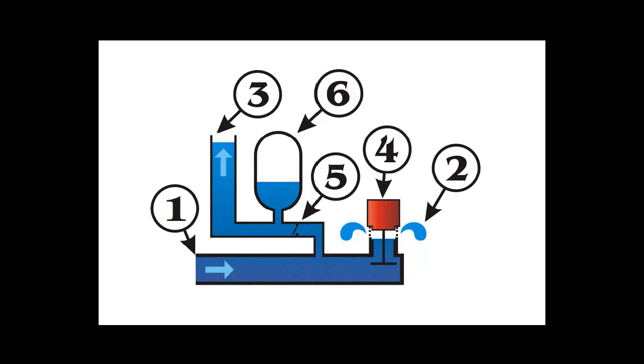A hydraulic ram has only two moving parts: a spring or weight loaded waste valve sometimes known as the clack valve, and a delivery check valve, making it cheap to build, easy to maintain, and very reliable. In addition, there is a drive pipe supplying water from an elevated source, and a delivery pipe, taking a portion of the water that comes through the drive pipe to an elevation higher than the source.